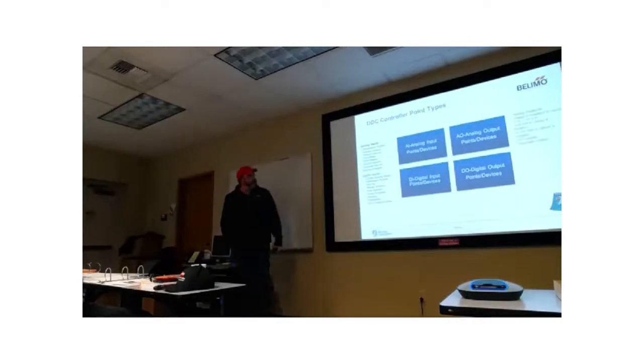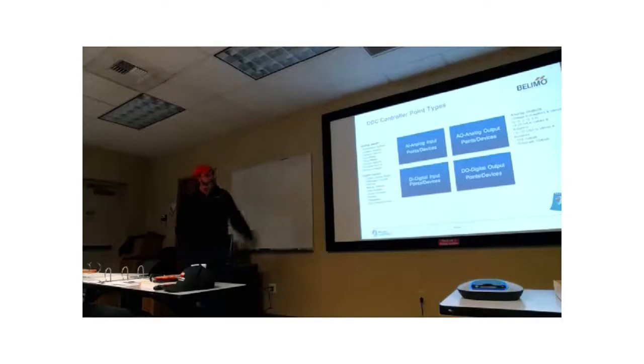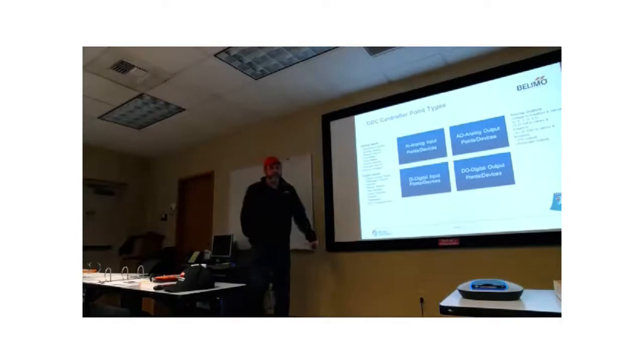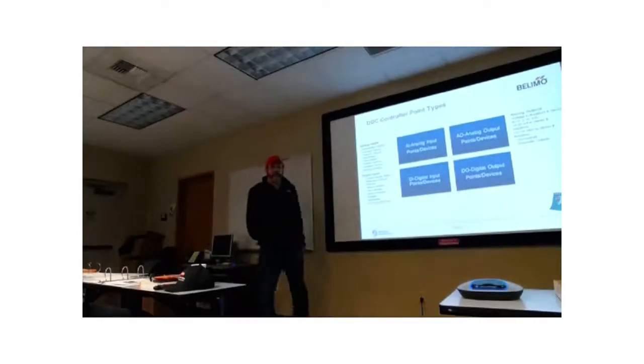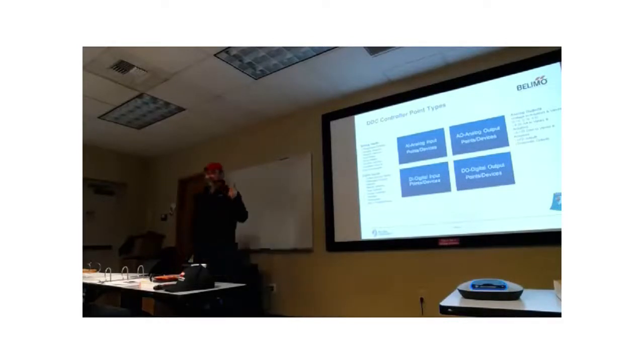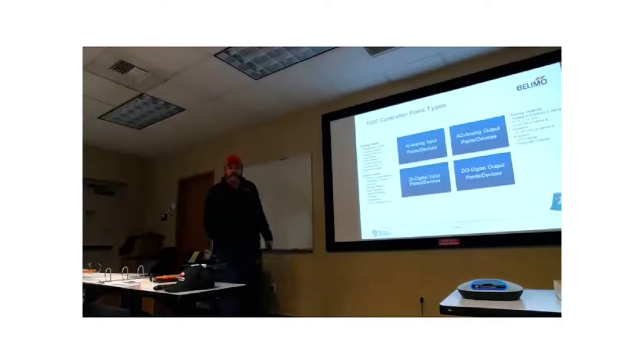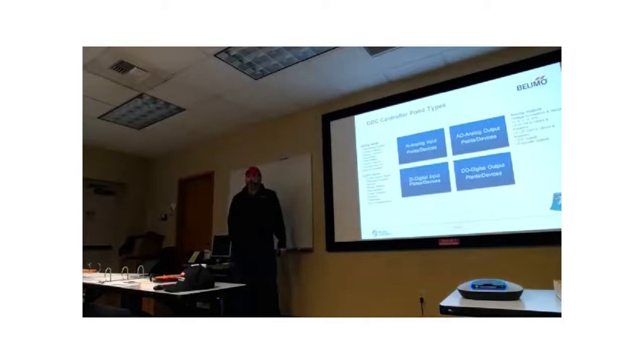The analog outputs are going to be any analog output from the controller. That would be that command signal I referred to over there. It could be 4 to 20 milliamps, it could be 0 to 5 volts. You guys are probably aware Honeywell makes an older Series 90 controller - its output is 0 to 135 ohms. A little bit weird, right? But that is its command output. It actually outputs resistance instead of voltage.